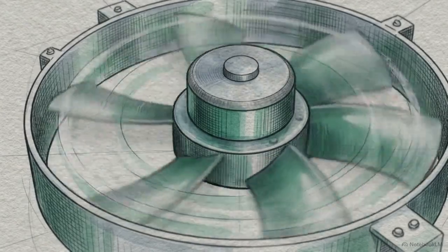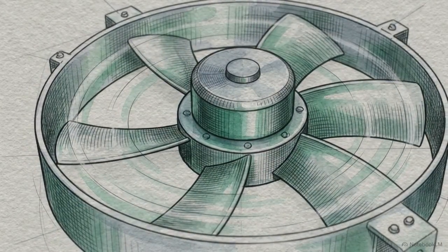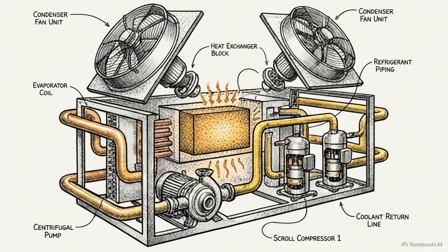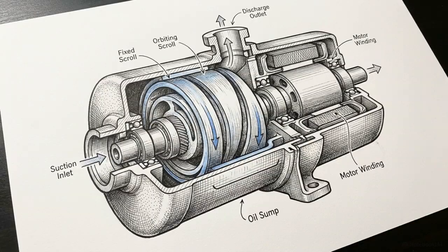It commands the pump's variable frequency drive to cut RPM, rapidly scaling down fluid velocity as the mechanical effort across the entire machine decelerates. This triggers a cascading mechanical reaction. The compressor slows down to match the reduced thermal flow, the expansion valve constricts its orifice, and the condenser fans drop their speed. A modern chiller functions as an integrated sensory network, with every component continuously hunting for mathematical equilibrium.